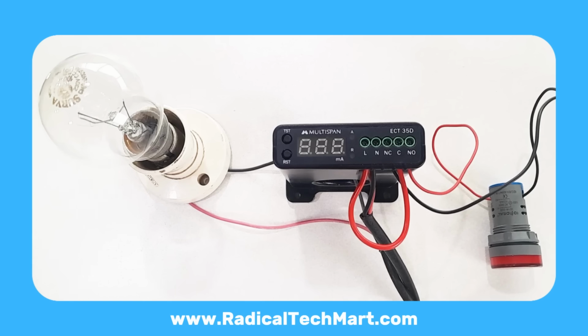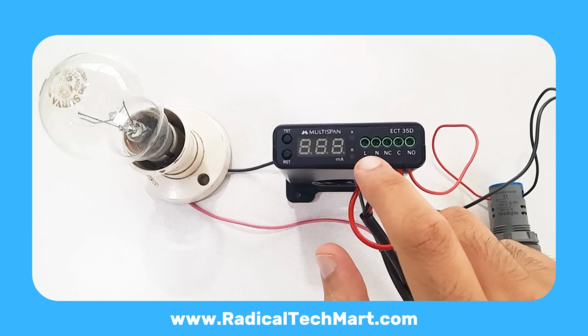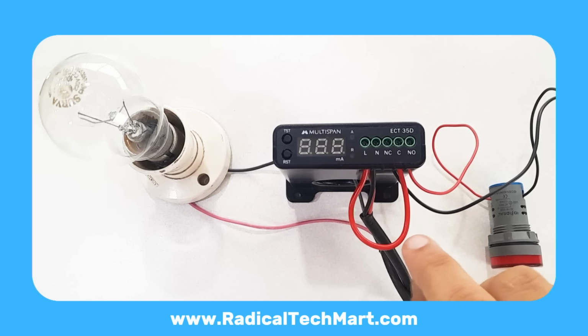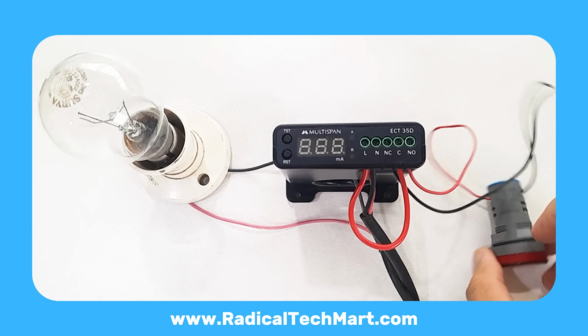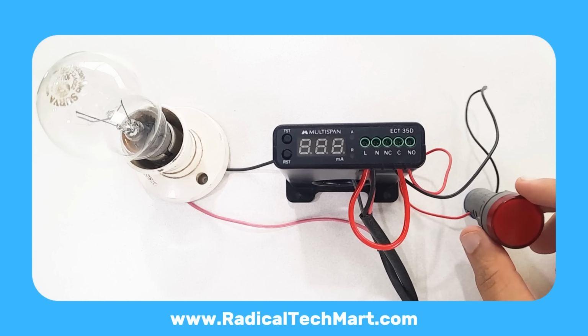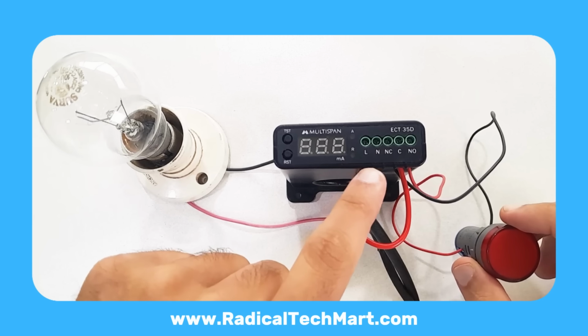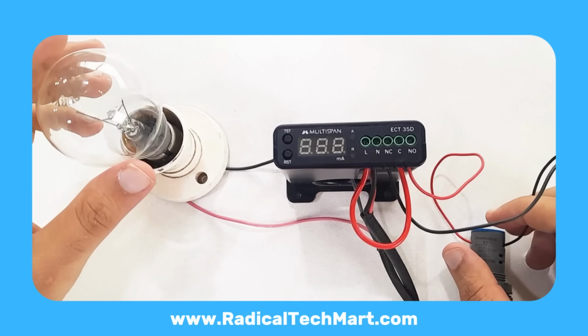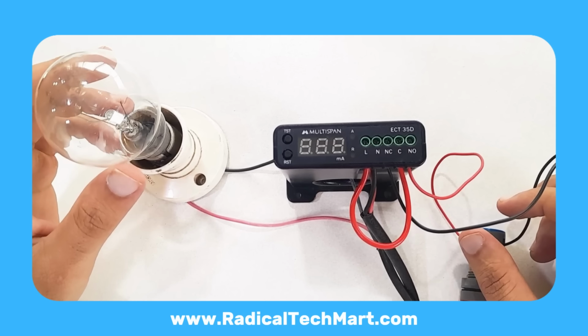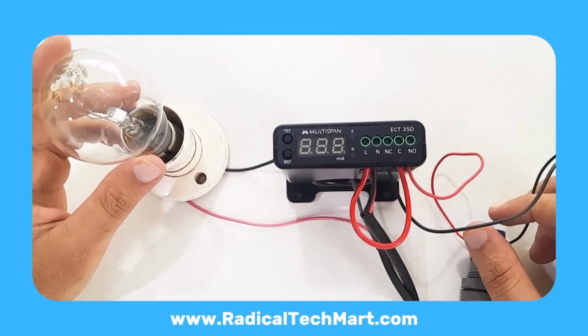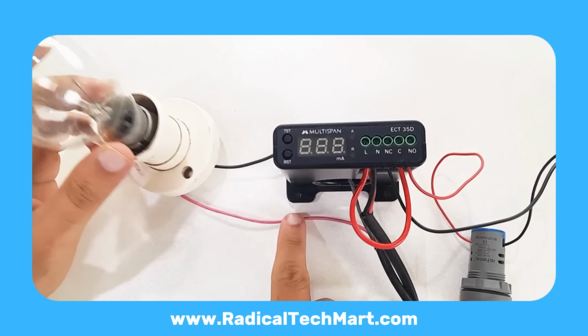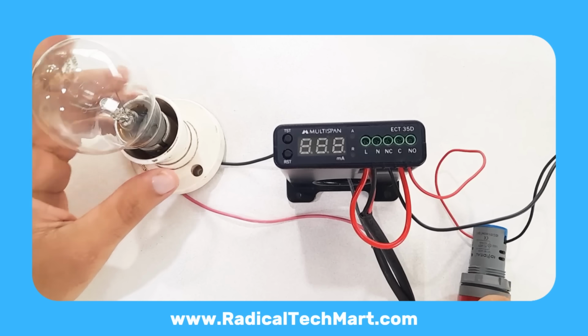Now let's move to the wiring setup. We've given line L and neutral N supply connections to the unit. From line, we've taken a short link to the common COM terminal. From the NO, normally open, terminal, we've connected an LED lamp, and the LED's neutral goes directly to the neutral line. To simulate a leakage condition, we've connected a simple test bulb.